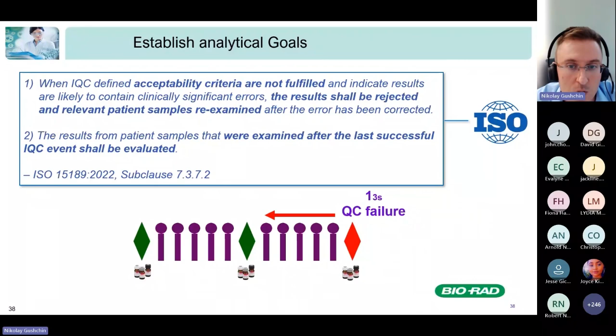Let's have a look at this situation. This is the regular statistics, the regular Levey-Jennings chart. At one point, in a lab, for example, we changed the reagent lot. And after the change of the reagent lot, there was a shift in the QC data, with the same lot of QC material, of course. They are trying to understand how this shift will affect patient samples, and if it's acceptable or not.